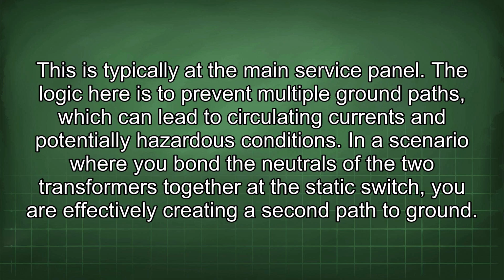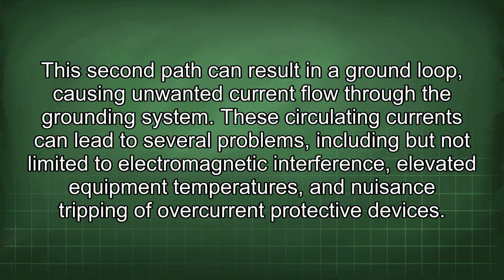In a scenario where you bond the neutrals of the two transformers together at the static switch, you are effectively creating a second path to ground. This second path can result in a ground loop, causing unwanted current flow through the grounding system. These circulating currents can lead to several problems, including but not limited to electromagnetic interference, elevated equipment temperatures, and nuisance tripping of overcurrent protective devices.